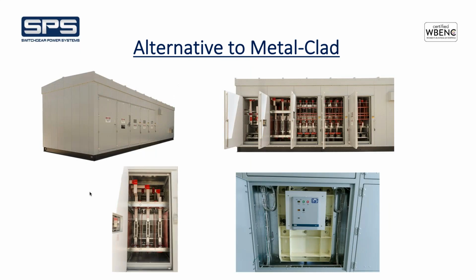So this is some pictures of the gear that I just showed the top view of the PDC for. So you can see the bus is insulated just like metal clad switchgear. Here's the 2000 amp incoming switch. This was the termination section, so terminating, coming through the bus through the switch. And then for the feeder breakers, it's the same terminations that you would expect in metal clad switchgear. So it looks and feels the same in terms of how you're going to terminate to the cables.